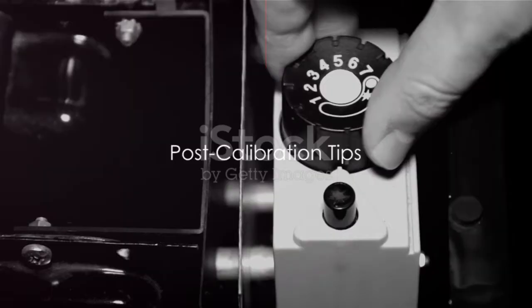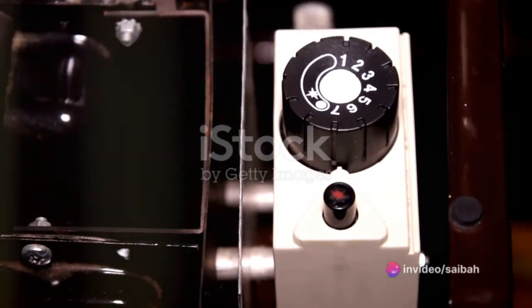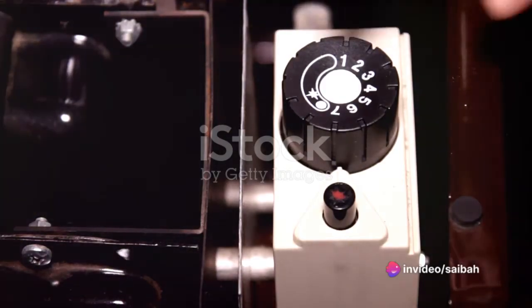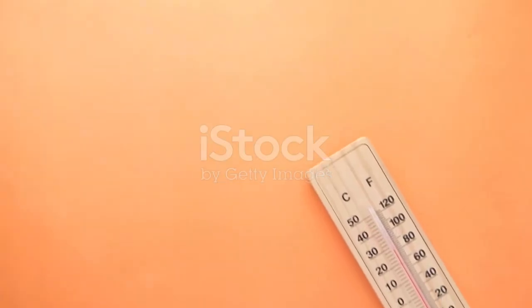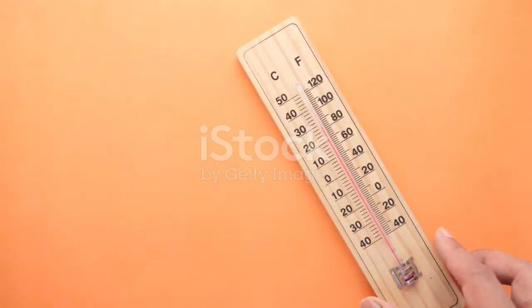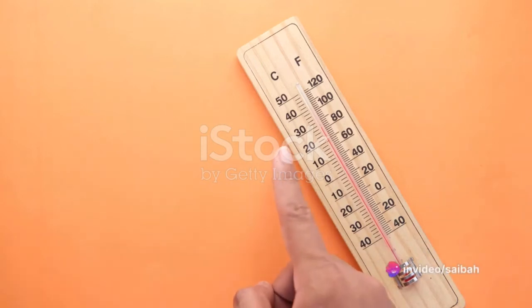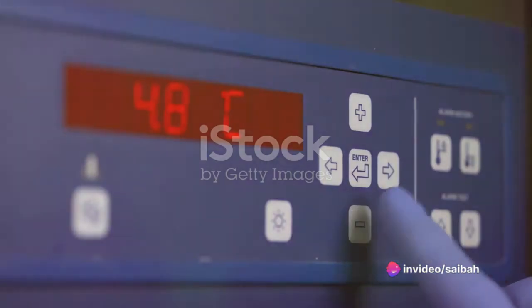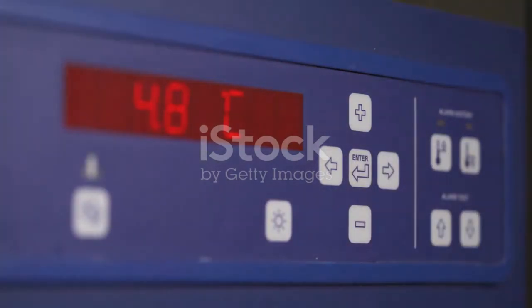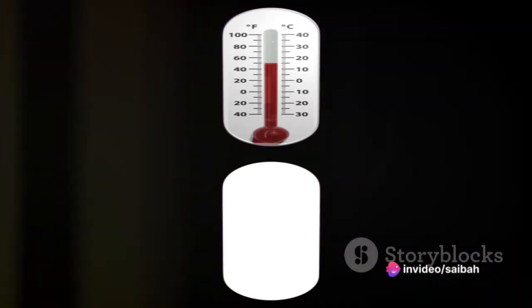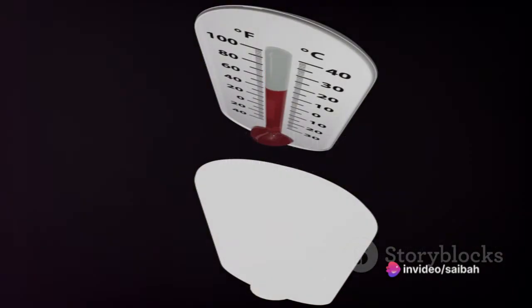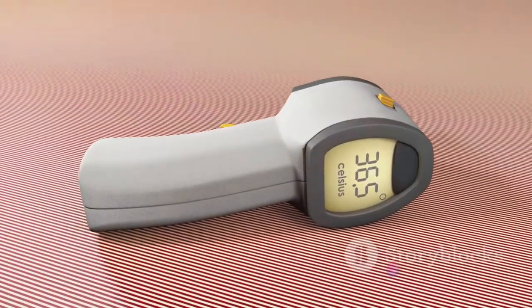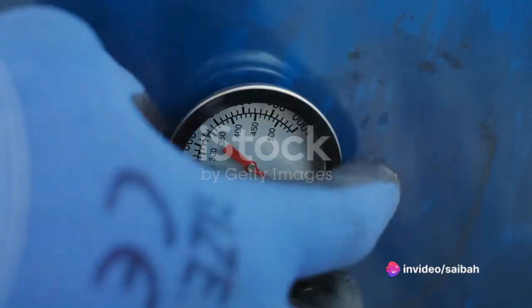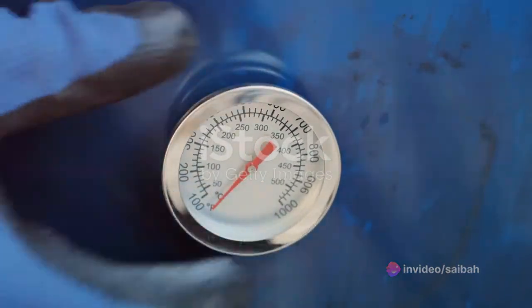Great job on completing the calibration process, but what's next? Now that you've successfully calibrated your temperature switch, it's crucial to maintain this accuracy through regular calibration checks. This is not a one-time task, but a continuous process to ensure that your temperature switch is always delivering precise results. Imagine this: you've just calibrated your switch, but it accidentally falls off the table or is exposed to extreme temperatures. What do you do? These incidents can impact the accuracy of the temperature switch, making recalibration necessary. So, always be mindful of these potential disruptors. And remember, temperature switches, like any other instrument, are not immune to wear and tear. Regular checks and timely recalibration can help detect and rectify any issues early on, reducing the chances of inaccurate readings. So keep your temperature switch in check.